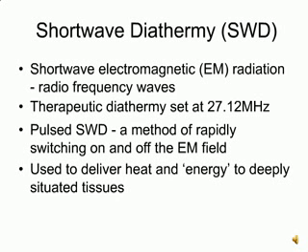Shortwave describes the wavelength of radio frequency waves. For therapeutic use, this wavelength is set at 27.12 MHz. It is a rapidly alternating current, alternating between positive and negative charge at this frequency. Pulsed shortwave diathermy, as with pulsed ultrasound, describes the rapid switching on and off of the electromagnetic field.